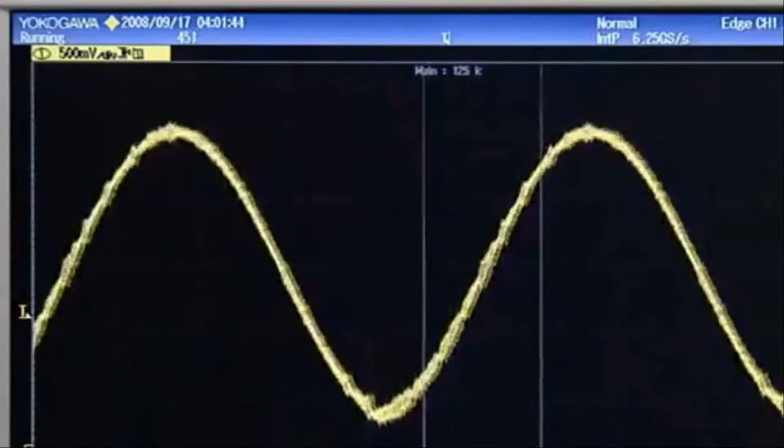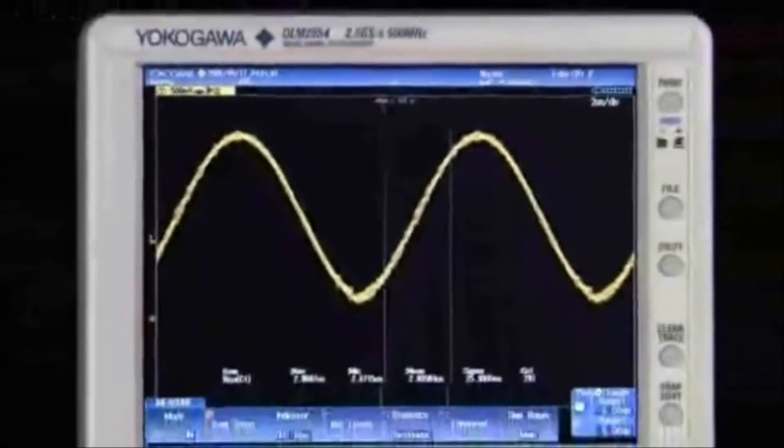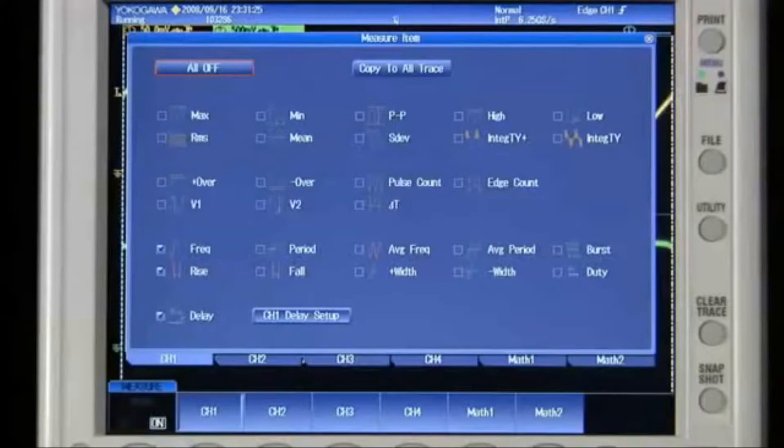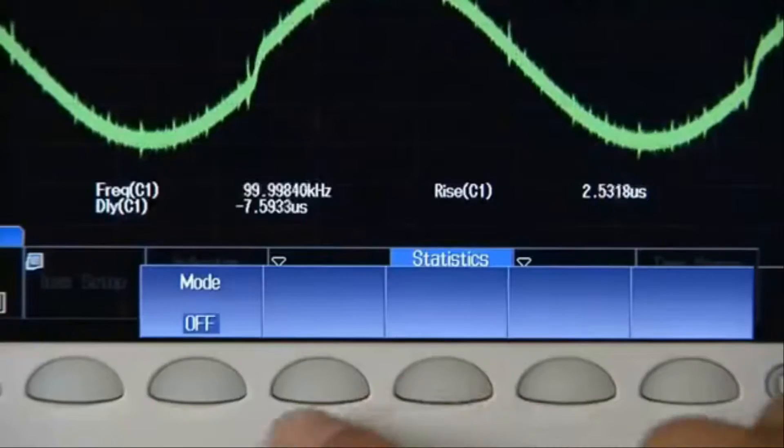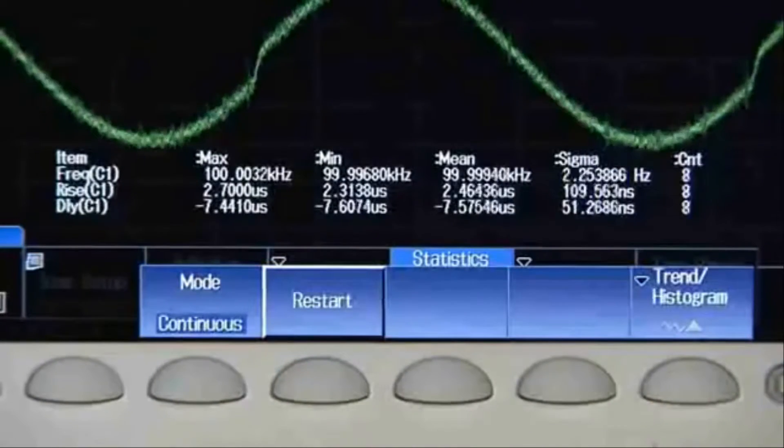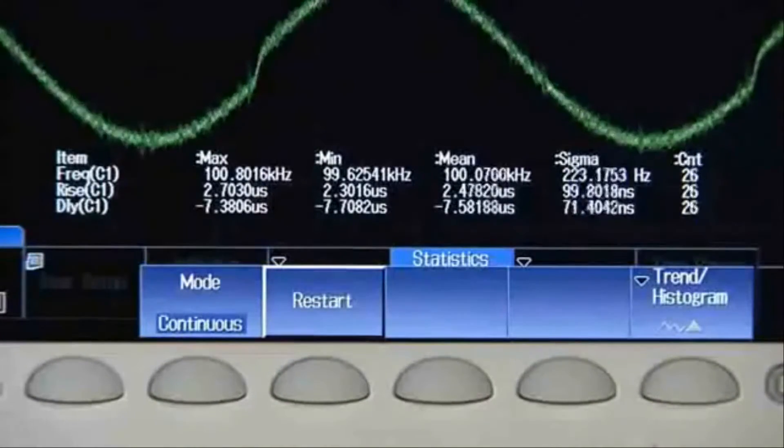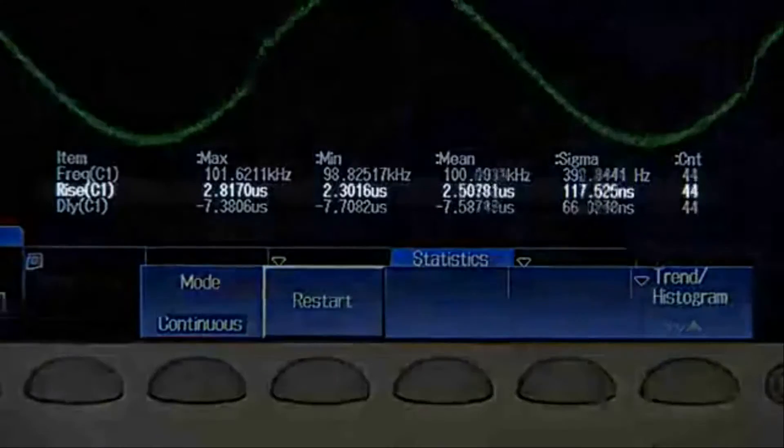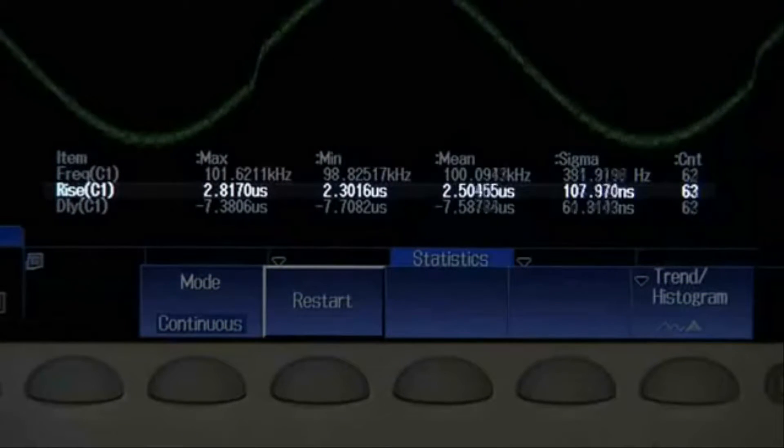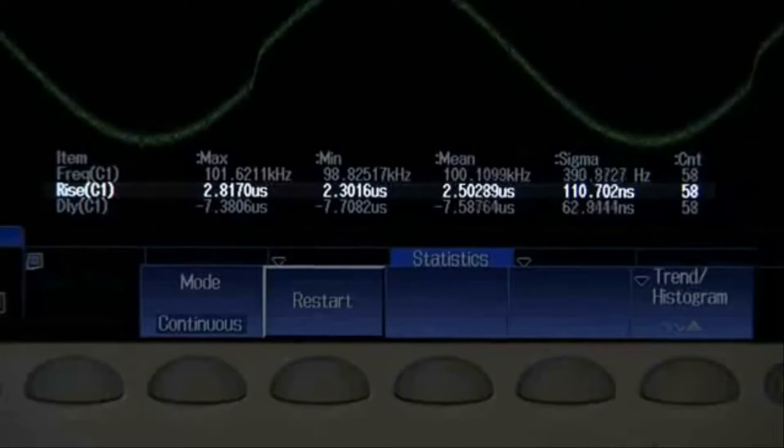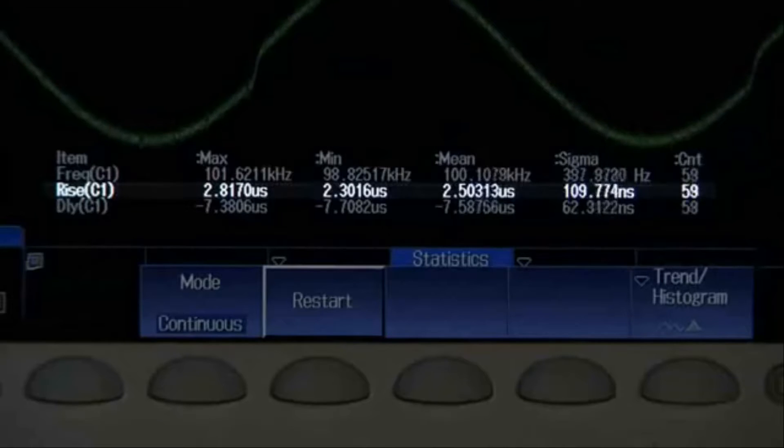Or let the Yokogawa DLM2000 make fully automated parameter measurements for you. Simply select from the parameter list and display up to 20 in real time. You can continuously calculate statistics for any parameters. For example, here we are calculating rise time statistics over multiple acquisitions, including max, min, mean, and standard deviation.